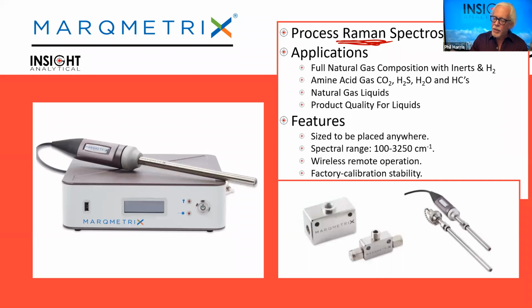Applications for this include doing full natural gas composition with inerts and with things like hydrogen. This is becoming important because as the world looks towards greener energy sources, people are starting to blend hydrogen into natural gas, and a lot of the existing gas chromatographs out there can't make that hydrogen measurement without significant modification. This technology can give us a very fast analysis of a natural gas stream, doing the C1 through C6 hydrocarbons, and the hydrogen, nitrogen, oxygens.